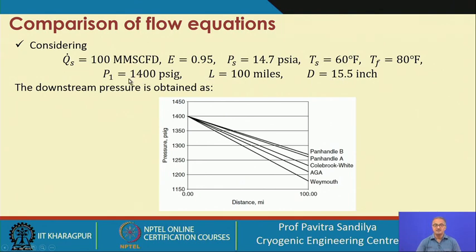Please note that the inlet pressure has been given in terms of gauge pressure. Before using any of the expressions to find the flow rate or friction factor, you must first convert gauge pressure to absolute pressure by adding 14.7 (the ambient pressure). Once you have the absolute pressure, you can use those various expressions to find the downstream pressure.